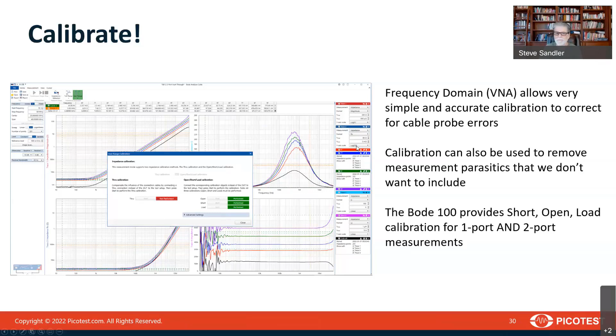Calibration does allow us to make really precise measurements at very low impedance. Here's how we measured 20 microhms. One of the things I highlighted in this university paper that I did this for is that we need to get incredible dynamic range. I showed that at 1 milliohm, we needed 87 dB. That means that at 100 microhms, we need 107 dB. And that means at 10 microhms, we need 127 dB plus the noise floor. So we're looking at somewhere around 140 dB dynamic range to measure 20 microhms accurately.